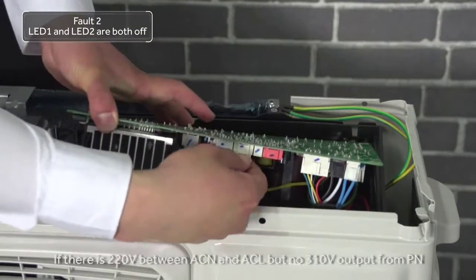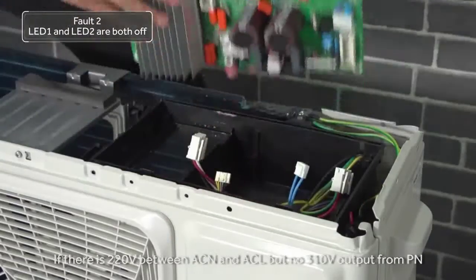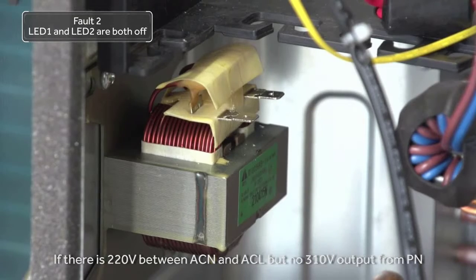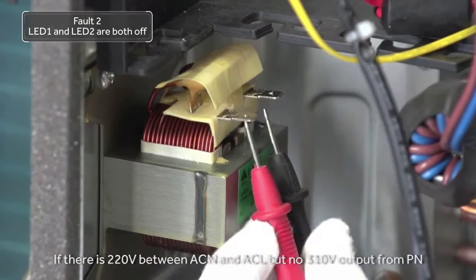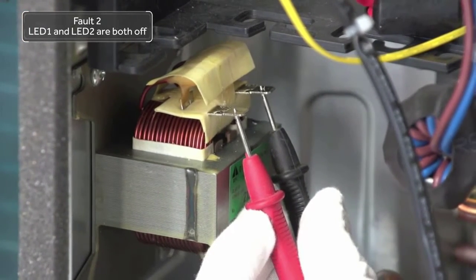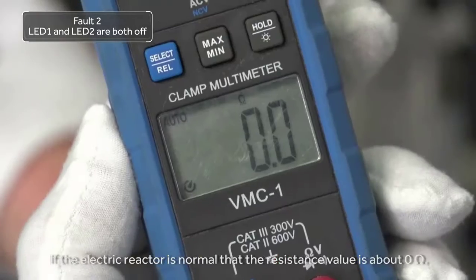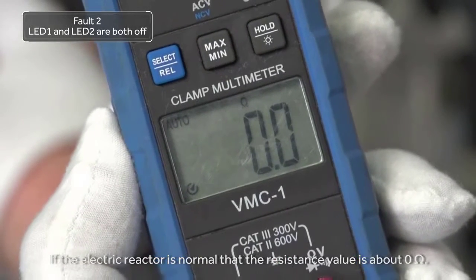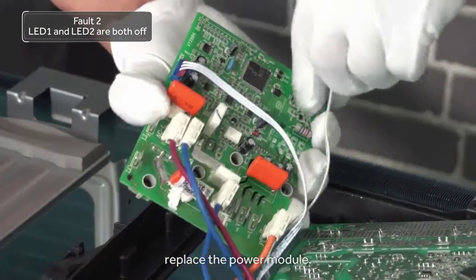If there is 220 volts between ACN and ACL, but no 310 volt output from PN, check the electric reactor. If the electric reactor is normal, that is, the resistance value is about 0 ohms, replace the power module.